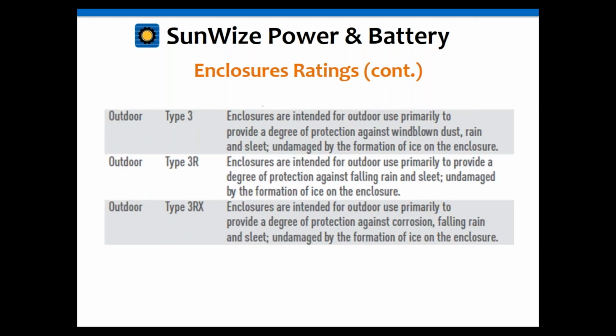For outdoor ratings, you normally hear about type 3, 3R, and 3RX. You may not hear a lot about 3RX, but it's basically the same thing as 3R, except using corrosion-resistant materials. That could be stainless steel, fiberglass, or even powder-coated aluminum, which is considered corrosion-resistant. Aluminum by itself, even though it has corrosion-resistant properties, is not considered X—you have to add the powder coating or anodizing to it. But generally it's powder coating, and that can give it that X rating.